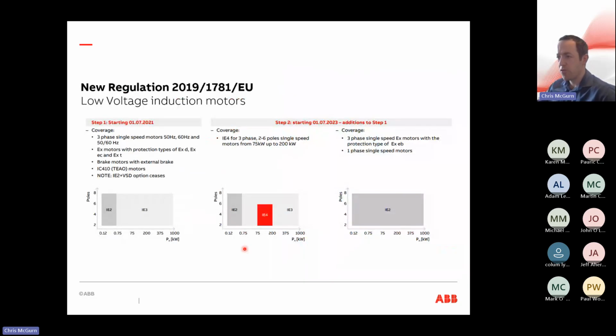systems. So these are the legislations that are currently in place for AC motors that are used typically on pumps and on fans. They have changed relatively recently, which some people may or may not be aware of, but the most modern one is here on the right-hand side, which was a new introduction that came out in July 2023. This graph shows the efficiency levels that are required for any motor that's being sold across a kilowatt band at the minute. So basically you've got IE4 here, which is the newest introduction.